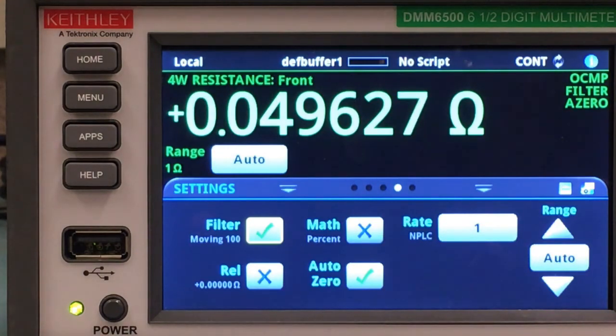Now you see we have a very smooth output of what we are trying to measure, which is our device under test of 50 milliohms. Notice that we are within the 1 percent tolerance, just above the 49.5 milliohm lower limit.